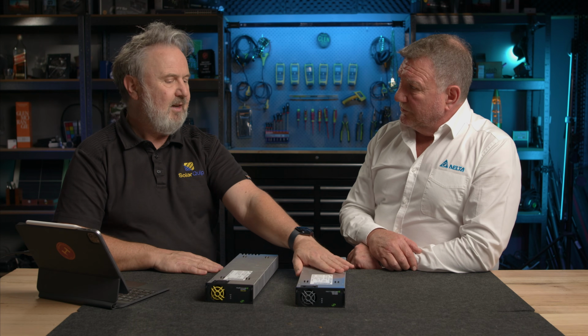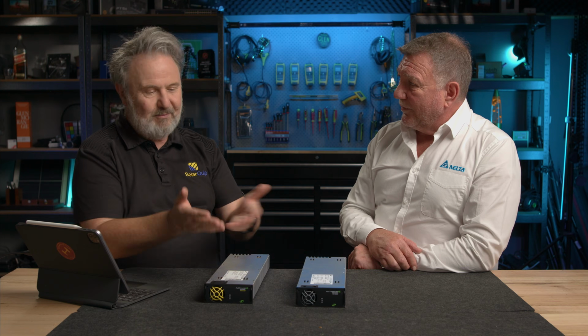So when you're doing a design, this is what got me really excited by this - separating these two components out. You design the rectiverters for the power demand the customer requires and the solar chargers for the energy demand. They're separate units, you don't have to have one for one anymore. But then all interacting together in a common backplane, managed by one controller.